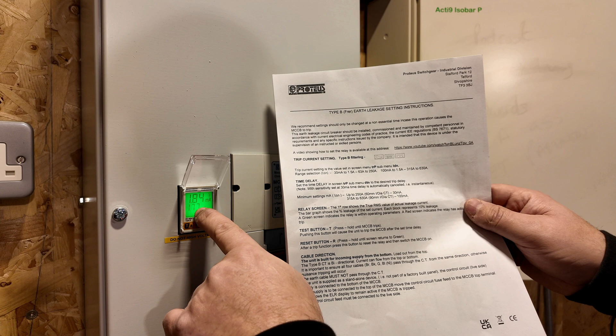You can have a time delay, but it says here with sensitivity set at 30 milliamps, the time delay is automatically cancelled, i.e. it's instantaneous. The relay screen shows you certain bits of information. So the bar graph shows the earth leakage, and you can see it here. If we scoot back out into the main menu, it will actually show you what's going on in the circuit itself. So you can see here at the minute we've got 1.83 milliamps of leakage that's going on.